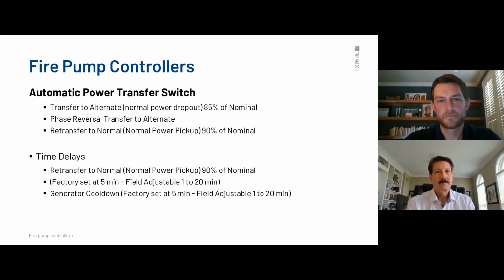Yeah, exactly. And also, once we do go back to normal power, the generator is going to have its own cool down process. We have a 5-minute timer, so you'll see a 5-minute timer running. The generator will still have voltage. At the end of that 5 minutes, the generator may shut off. Sometimes they have their own internal timer as well. So it could run for another 20, 30 minutes, depending on how that generator is set.